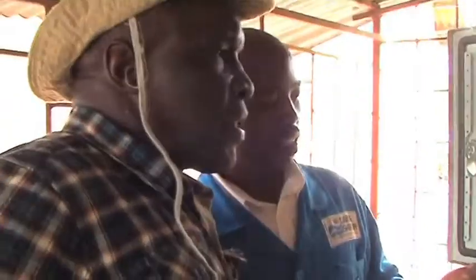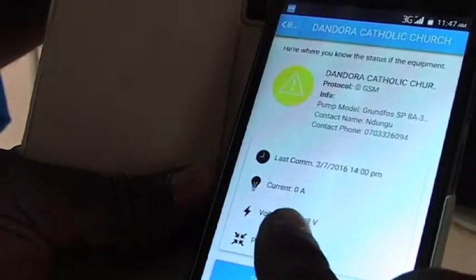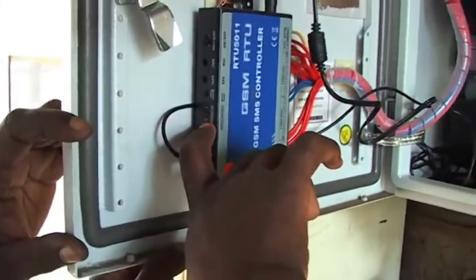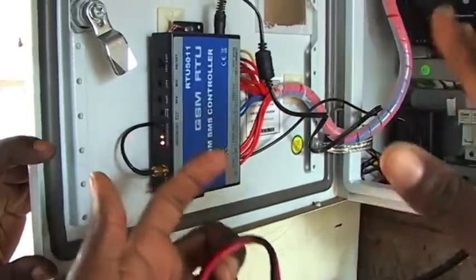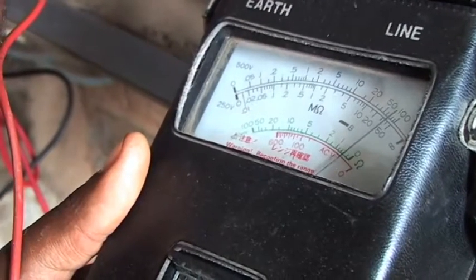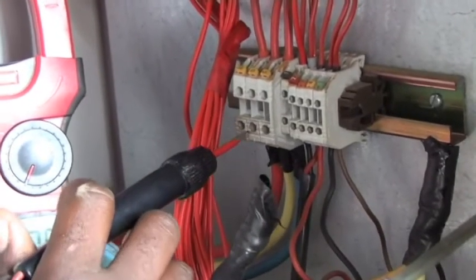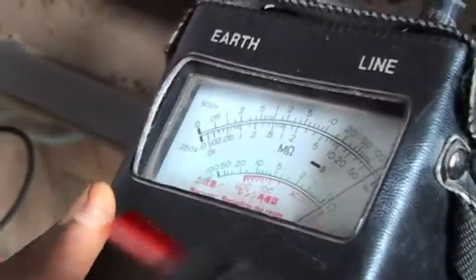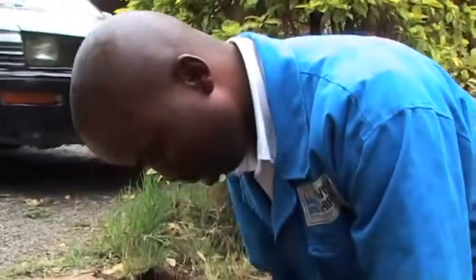This is showing me 48, and the problem is that it is showing zero current. When you see the red breaking like this, that means there is a network. When you see these other ones, that means there is some sending and receiving of a signal. When I see this, it tells me there is some problem with these windings — this is the road going to the motor down there. There is an open cable here.